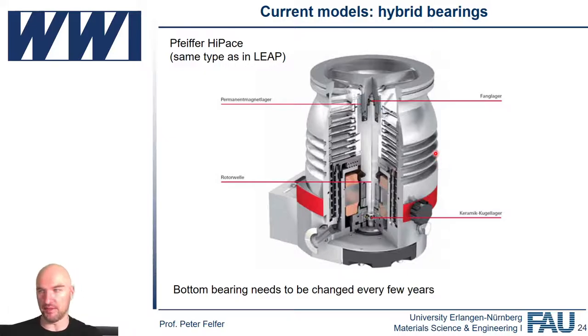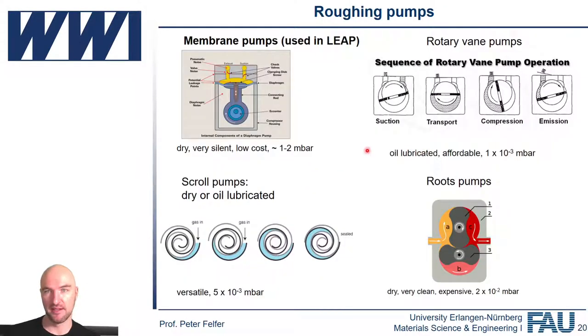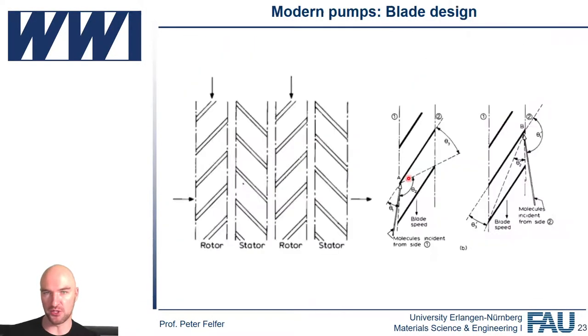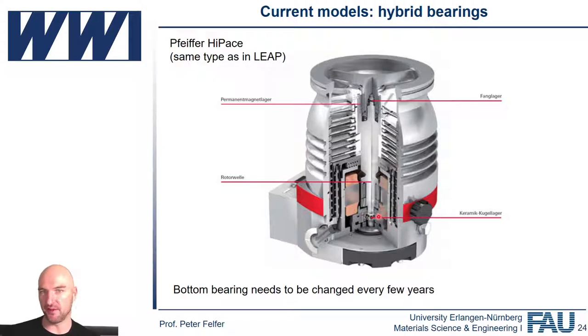The good thing about these pumps is they're extremely clean. They can get you from backing pump pressures down to UHV, and we'll see that getter pumps cannot do that. Essentially, they get you from the pressures that these pumps leave us at down to UHV. And they're very clean and very easy to maintain. All I need to do is change the bottom bearings every couple of years.